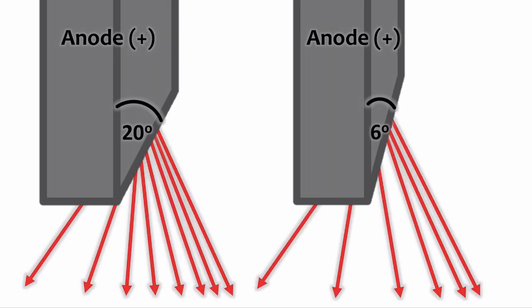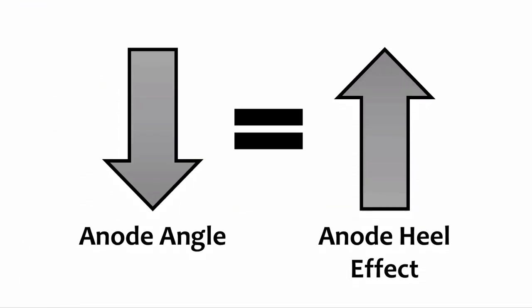A few variables can actually change the extent of the anode heel effect — in other words, the change in beam intensity across the beam isn't always the same. Decreasing the anode angle, making it steeper or smaller, increases the anode heel effect. This is because more x-rays get absorbed in the anode and the beam intensity on the anode side decreases. When we decrease the anode angle from 20 degrees to 6 degrees, an increased number of x-ray photons get absorbed, resulting in an increased difference in intensity between the anode side and the cathode side. The relationship between anode angle and the heel effect is inverse: as the anode angle decreases, the anode heel effect increases.